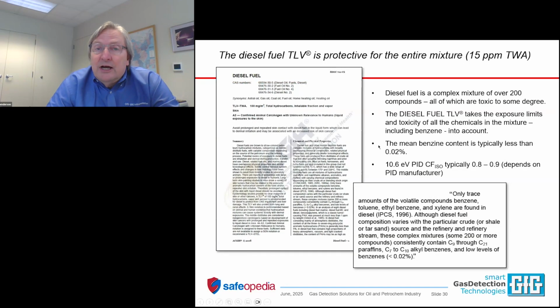Now, for diesel, the reason the TLV works at 15 parts per million is because such a small fraction of the diesel vapor comes from benzene. The benzene content in diesel is typically less than 0.02%. So if all you're measuring is benzene and you're ignoring the rest of the VOCs in the diesel vapor, or you're just dealing with it from the standpoint of LEL combustible gas, you're omitting the measurement of 99.98% of the toxic VOCs that are present.